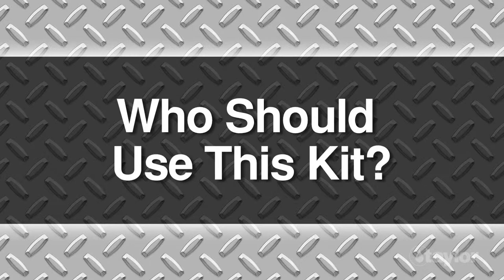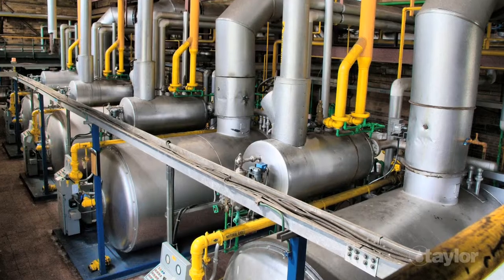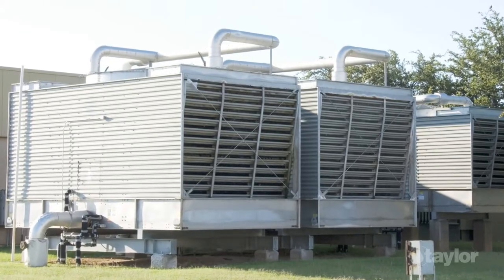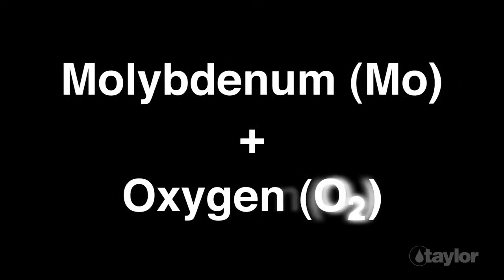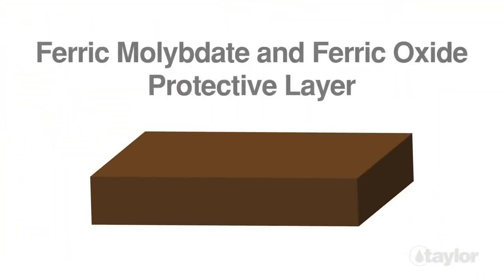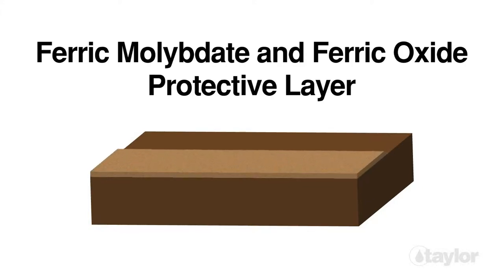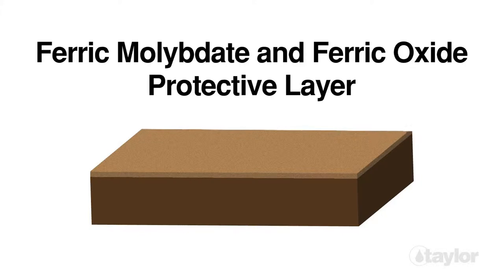Who should use this kit? Molybdenum-based products are used in boiler and cooling towers to inhibit corrosion. In these aqueous systems, the molybdenum combines with oxygen to form molybdate. The molybdate is then adsorbed onto the porous metal oxide surfaces where it reacts with the iron. This reaction produces an insoluble film of iron molybdate that protects the metal from other ions that induce corrosion.